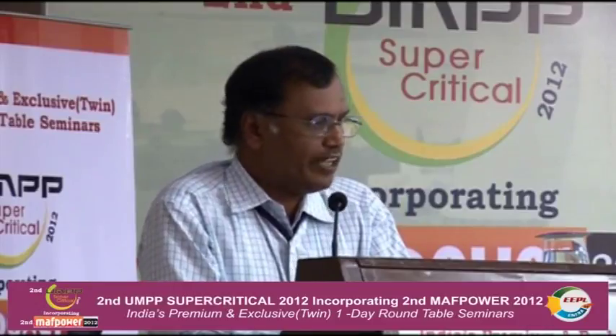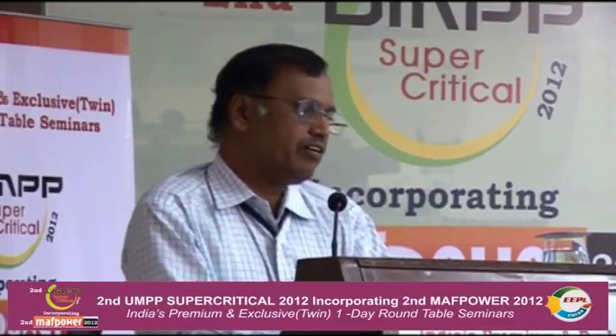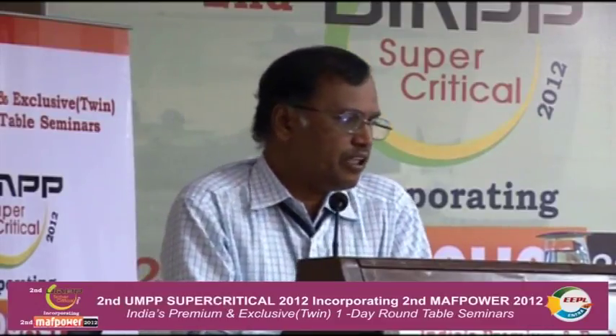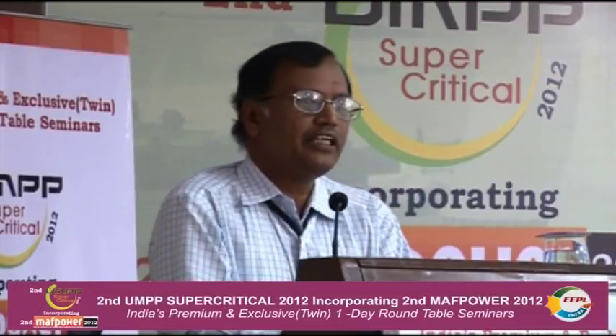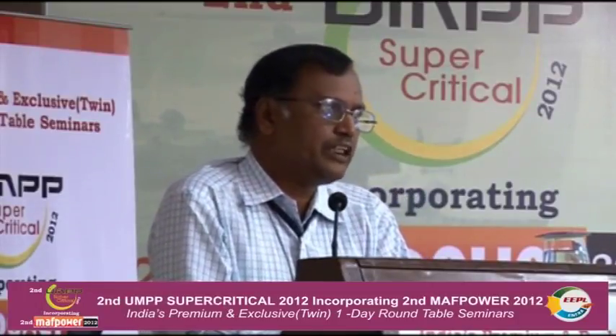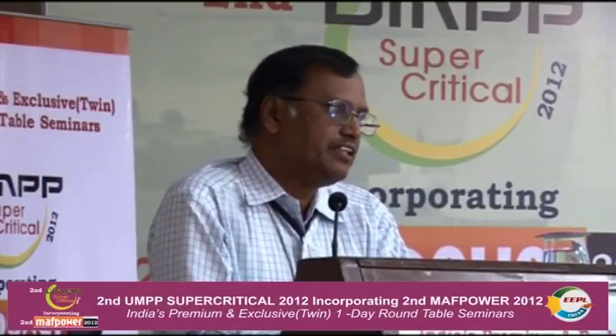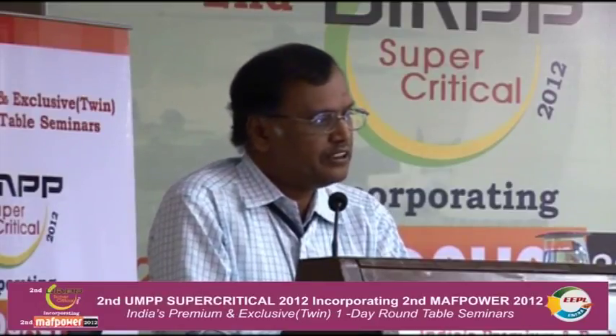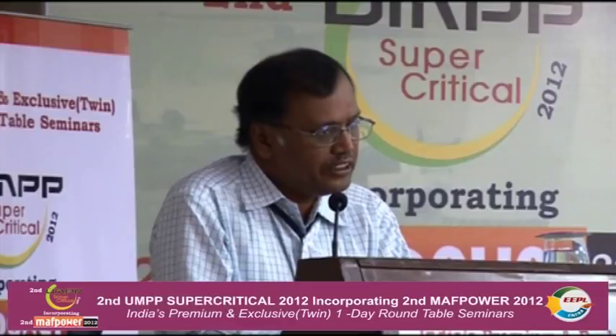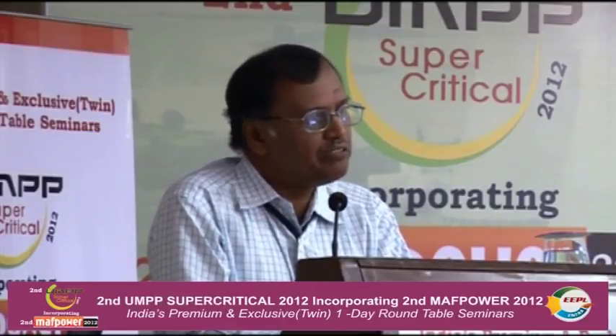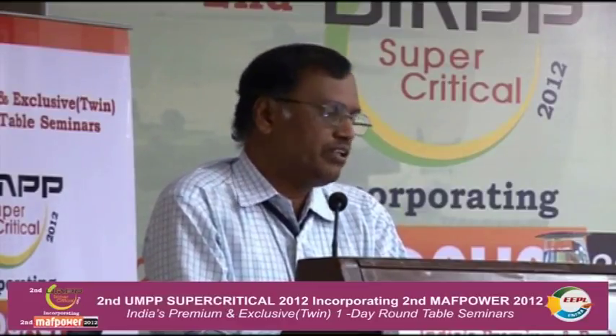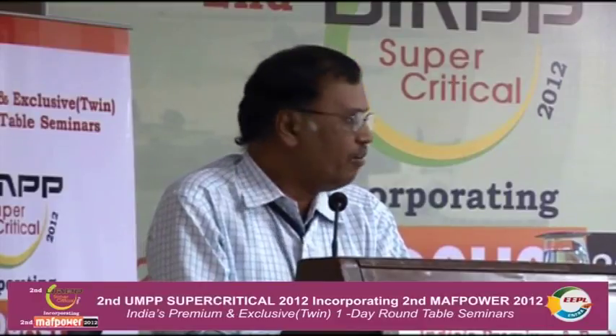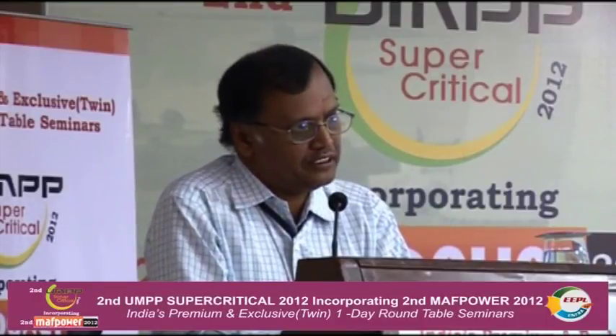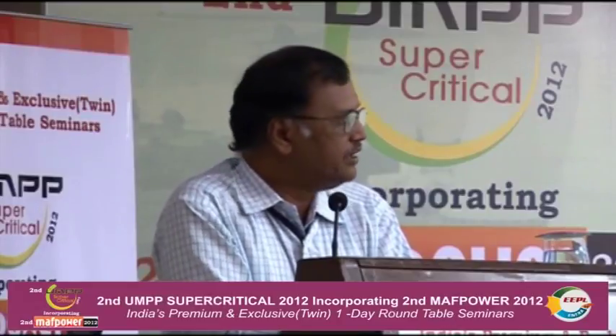And all the fans are axial, including ID fans. Normally in subcritical boilers, even now up to 500, 600 megawatt, we give only radial fans because we are worried about the dust loading in the flue gas. But because of the stringent emission norms, we are having a very good ESP. We are now giving axial fans for ID also. Virtually all FD, PA, ID, all the fans have now been converted into axial fans. This is another improvement in the supercritical design.